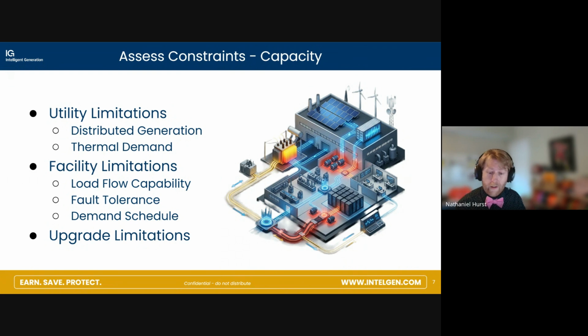Similarly, depending on how your conductors are built and where you're interconnected, if your battery is charging at full speed, your solar is contributing at full speed, your site is using a full amount of power, and you're connected to the utility, depending on whether those junctions overlap, you might create a spot with twice as much power flowing through the conductors as expected.